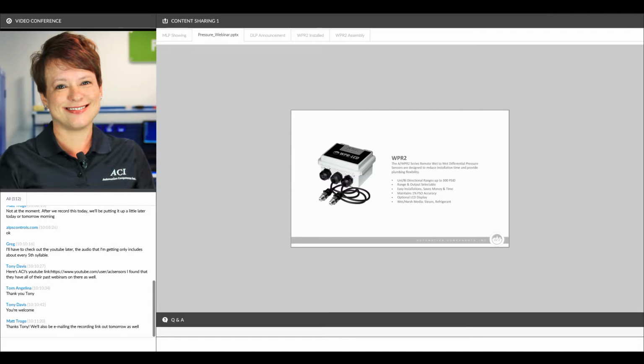So you can carry those transducers right up to the taps on your pipes and thread them on. You do not have to do all of that copper piping like you would have to if you're using a unit where the sensors are fixed in the housing. So because you're not doing all that copper piping, you're not building in a lot of air that needs to be bled off on the startup process. And the fact that we're using the independent pressure transducers, which give you very high proof and overpressures, is also going to get you away from needing any type of bypass valve assembly. So this should not only be a time savings for you, it should also offer some parts cost savings.